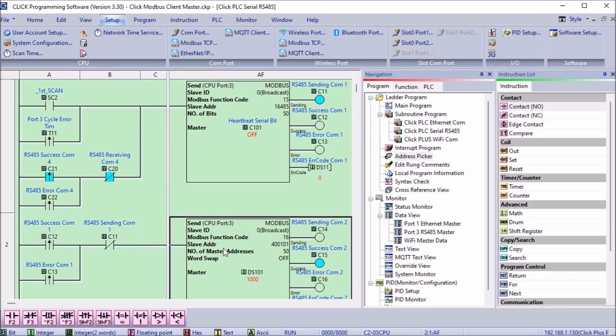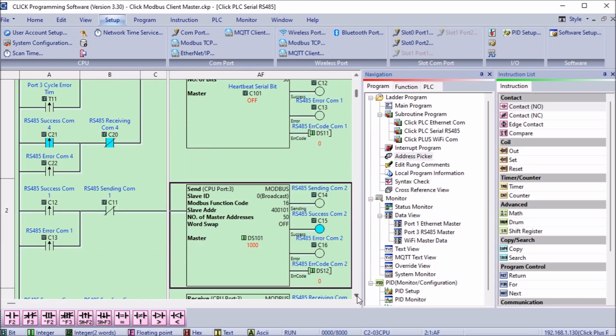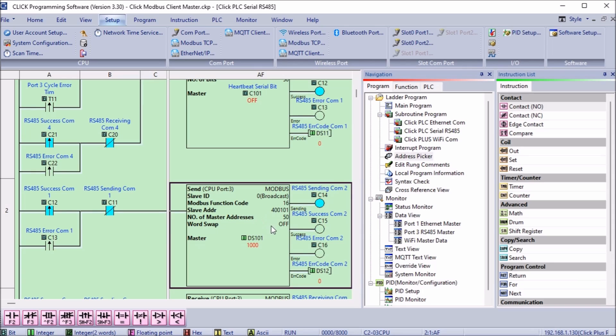Our next send instruction will use the write multiple registers. The starting slave address will be 400101 which is DS101 in the Click PLC. We will write 50 registers. Registers DS101 to DS150 from the master PLC will be written to DS101 to DS150 of the slave PLC.